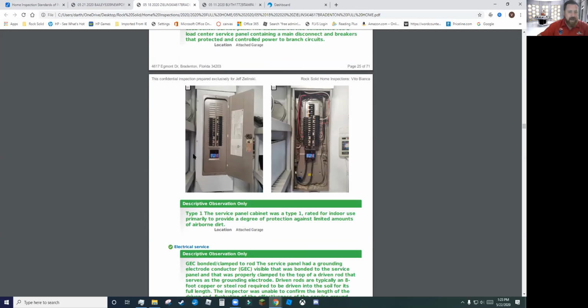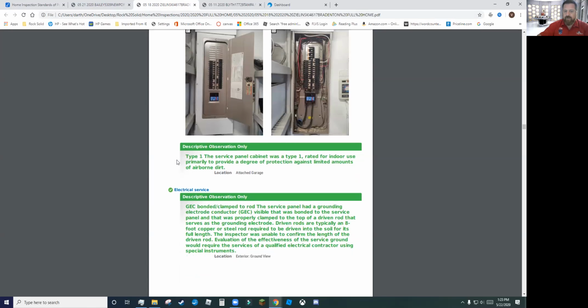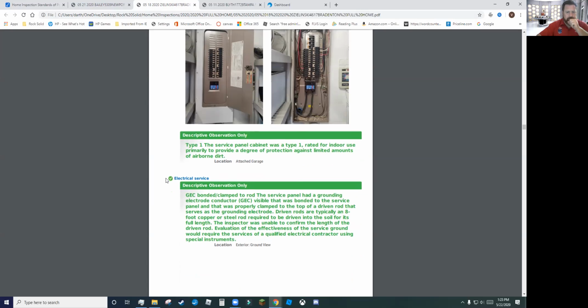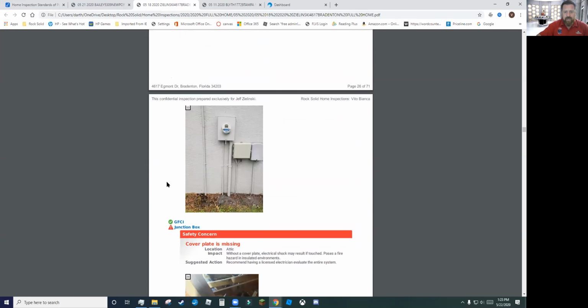Load center service panel—this one was really clean. It was a type 1, which is less important when it's inside, but if it's an outside panel, you do want to verify that at the very least it's a type 3R that's actually rated to protect the wiring against moisture intrusion, dirt, dust and wind. Again, the GEC was bonded and clamped to the rod.